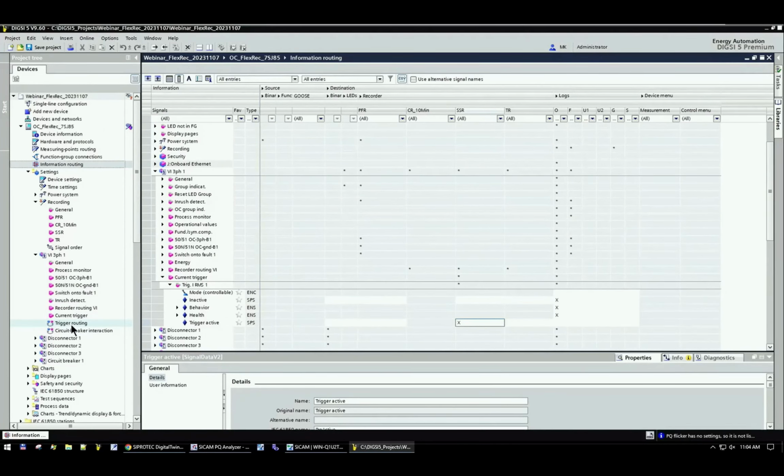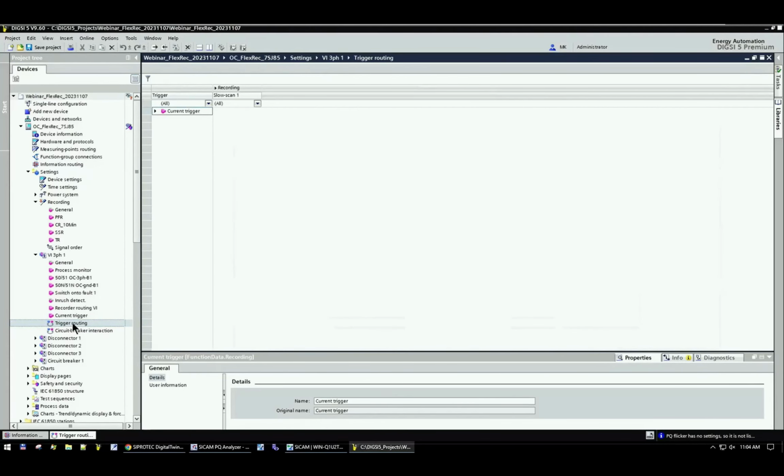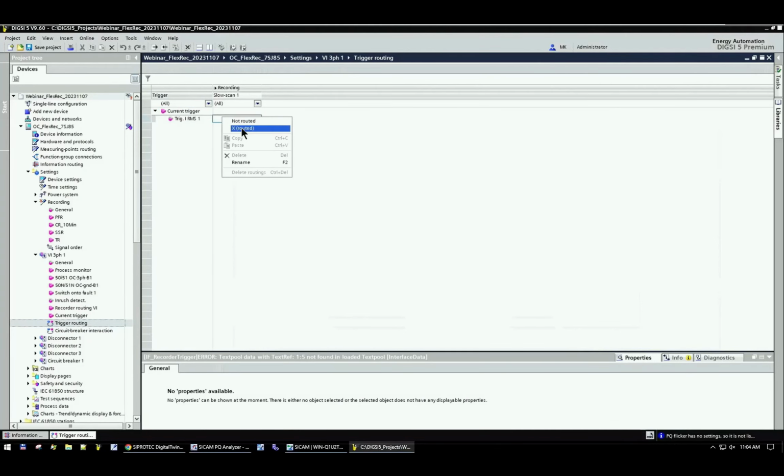We have to take a look inside the trigger routing. And in the trigger routing, we now also find our current trigger of IRMS. And we want that when this trigger becomes active, a fast scan recorder is started and the slow scan recorder started. fast scan is 7SJ85. Okay, that means above 0.9 amps, the binary track will be added into the slow scan record, and this trigger routing takes care that the slow scan recorder starts recording.